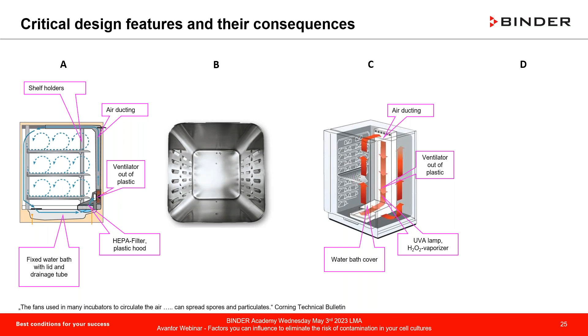D is the version where you once again have an air ducting system. I confess it is smaller than C and A, but it's still more contamination-prone than, for example, B. You have a ventilator inside and air circulating around it. I hope you've noticed that one sentence below—this is also from the Corning Technical Bulletin. A quote: the fans used in many incubators to circulate the air can spread spores and particulates. And that is a big benefit of B, because we don't have any fan inside in that case.